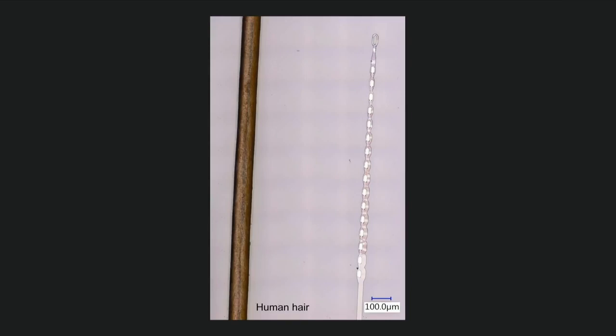Notice that this thread is thicker at the bottom of the image and thinner at the top. That's because each of the tiny gold wires is separated from the others by an electrically insulating material so as to prevent channel crosstalk. More gold wires means a thicker thread. And as you go from the bottom to the top, one gold wire after another terminates into an electrode. So fewer insulated wires need to run to the more distal points on the thread, meaning that the thread size can taper as it gets closer to the distal end.